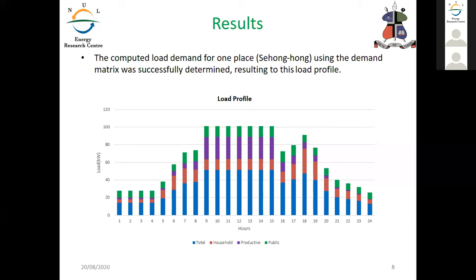The next question: what are the component differences between 99% and 100% reliability that lead to such a dramatic difference in LCOE? For example, does 99% use less battery storage? The battery storage basically is 5 times greater. When you design for 100% reliability, it requires a very big system, which will involve a very big storage battery. And like I said, the storage battery is the most expensive component of the mini grid system.